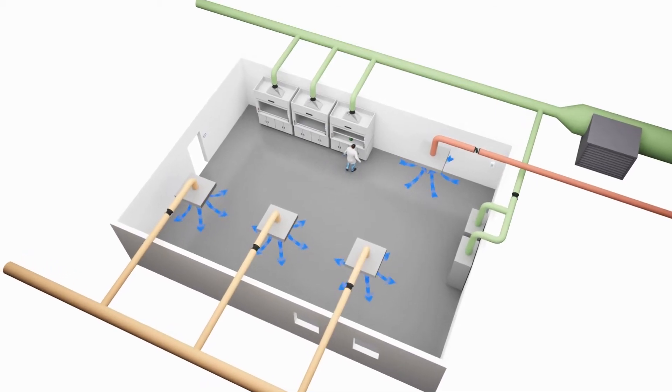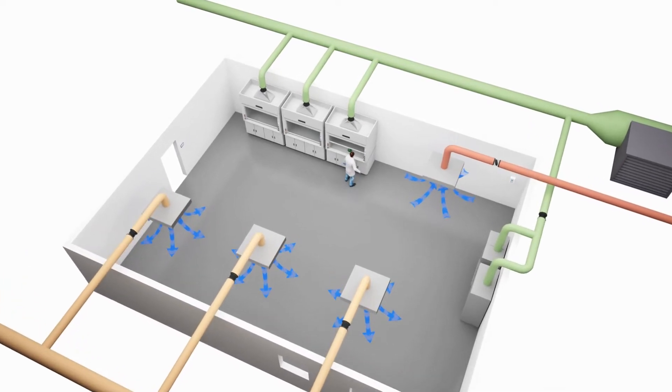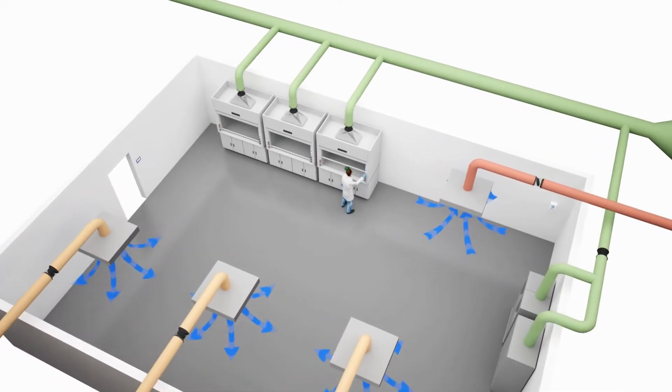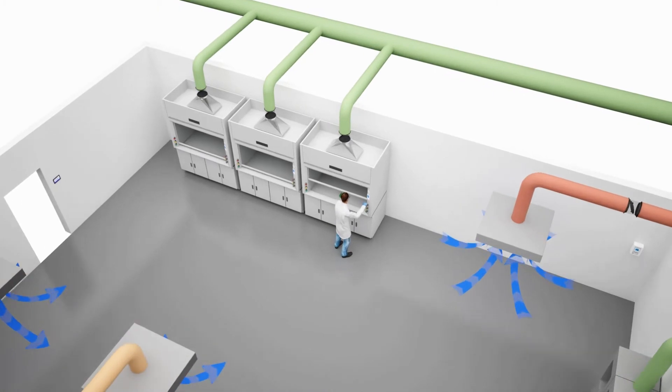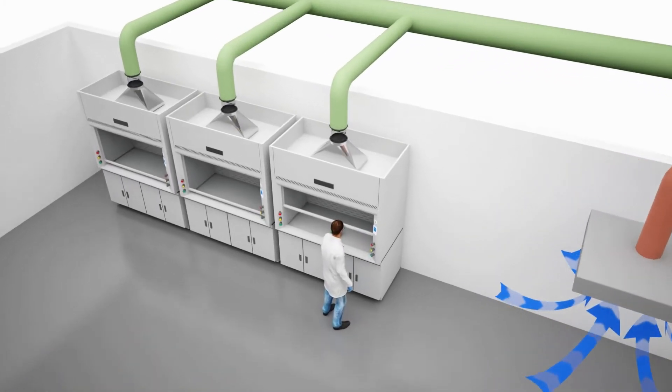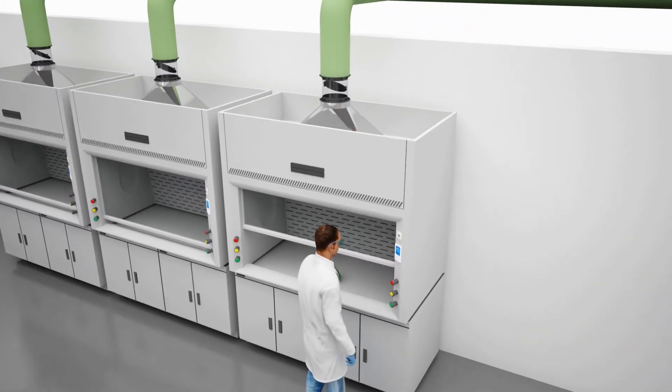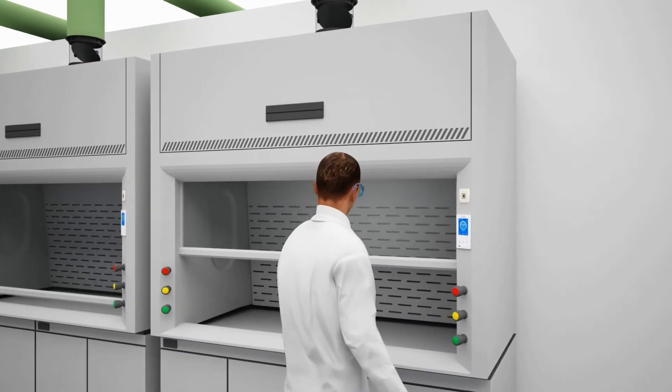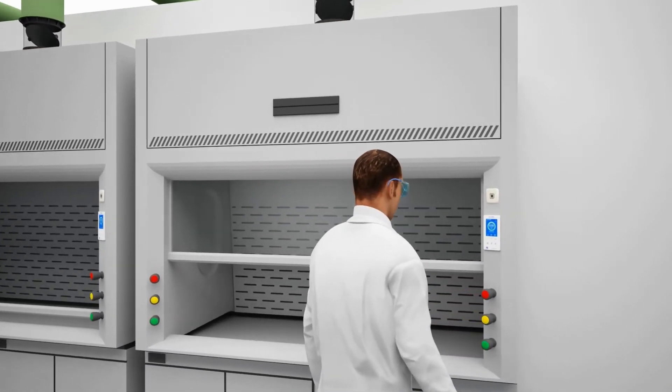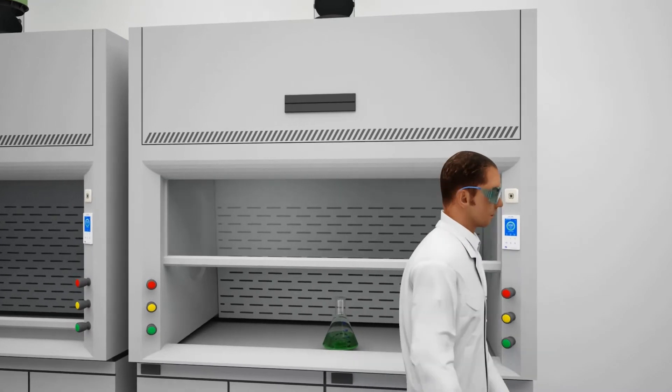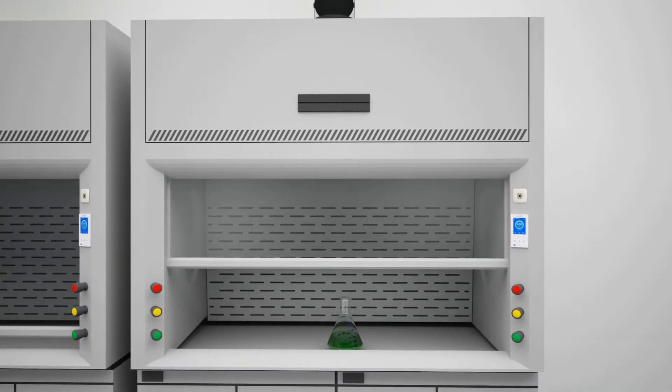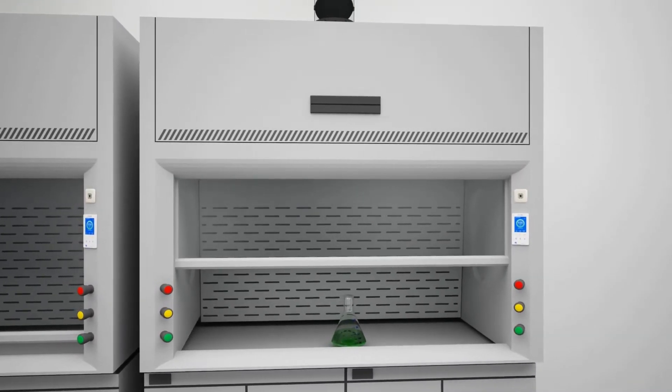TEL's innovative auto-sash controller for fume hoods maximizes energy savings and provides increased safety for the operator. We've specifically designed our auto-sash controller to close the sash automatically when the operator is not present in front of the fume hood. This system works through a passive infrared sensor that constantly monitors the work area in front of the fume hood.